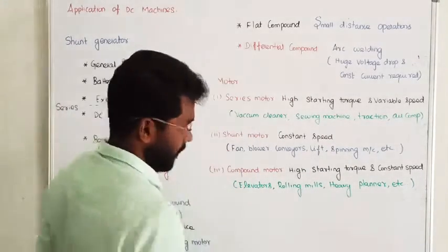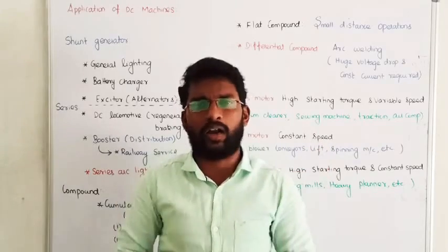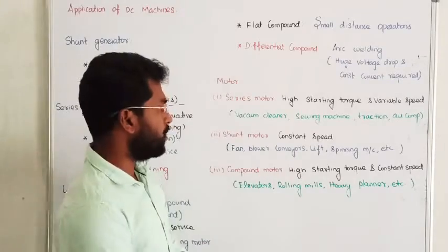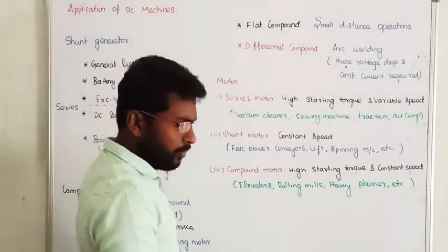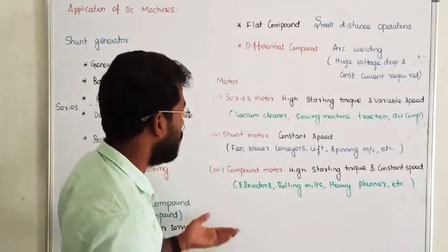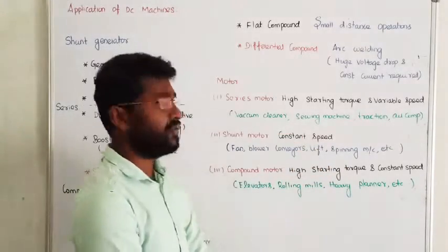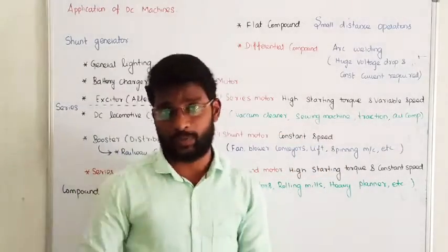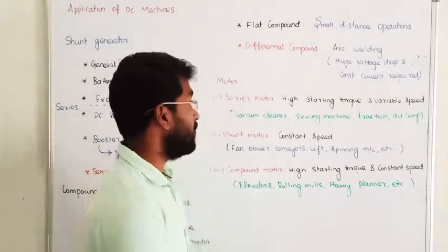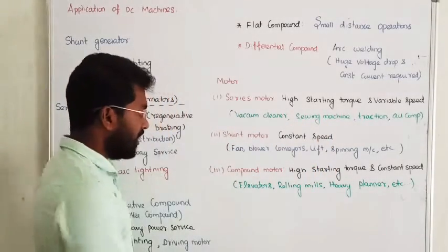Next, we discuss the shunt motor. The shunt motor provides constant flux, or we can say constant speed. Speed on constant torque is provided by the shunt motor. Shunt motors are usually used for constant speed applications such as fans, blowers, conveyor belts, lifts, and spinning machines. However, the problem with the shunt motor is that starting torque is not very high.